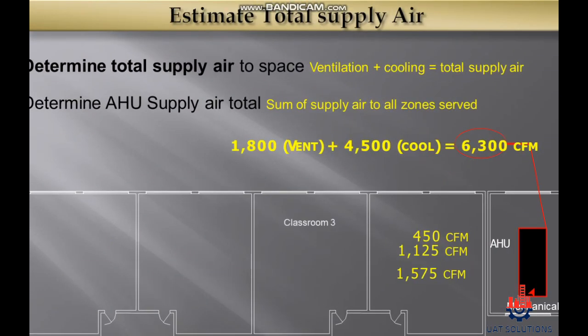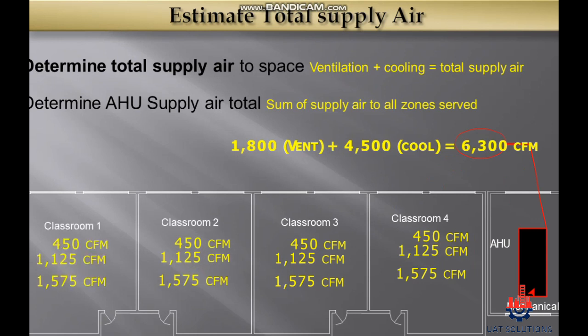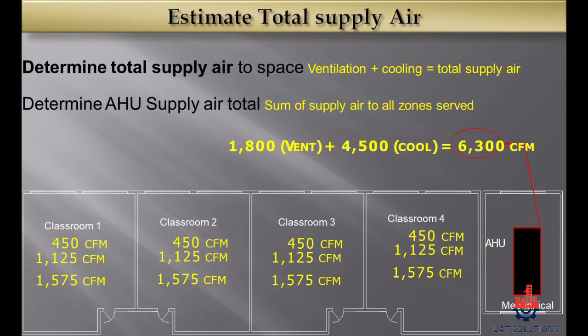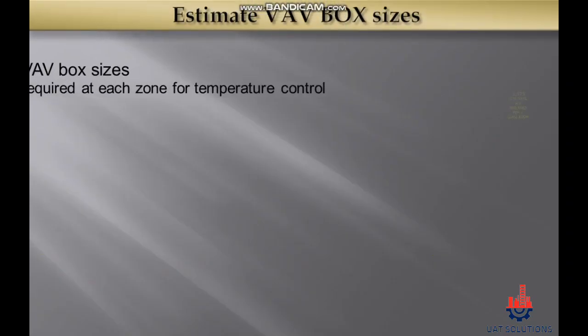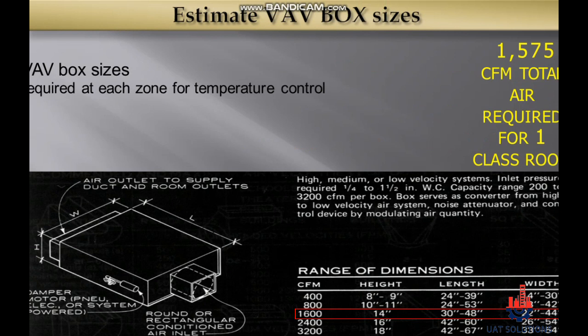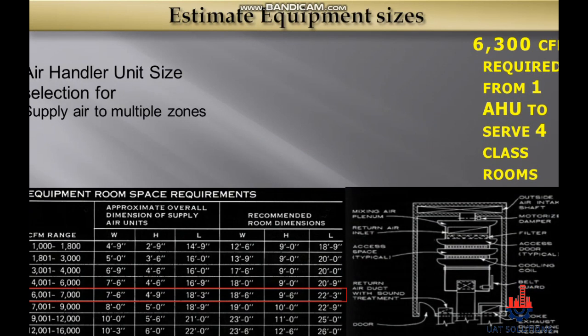Now that we have calculated the CFM for space cooling load and ventilation load, let's estimate total CFM for total supply air. Space cooling load for one classroom is 1,125 CFM and ventilation load is 450 CFM, totaling 1,575 CFM per classroom. With four classrooms, total supply air is 1,575 multiplied by 4, which equals 6,300 CFM. We will need a VAV box that can supply the required CFM, and an air handling unit that can supply 6,300 CFM or at least 10% above actual requirement.